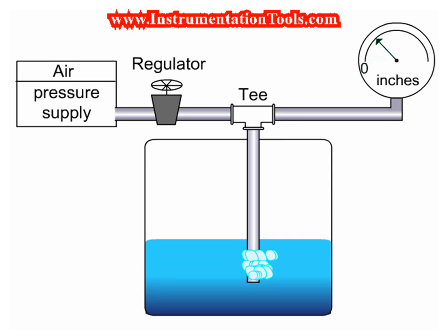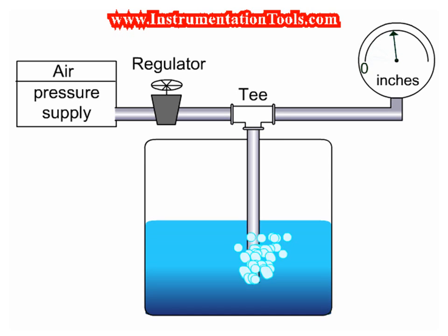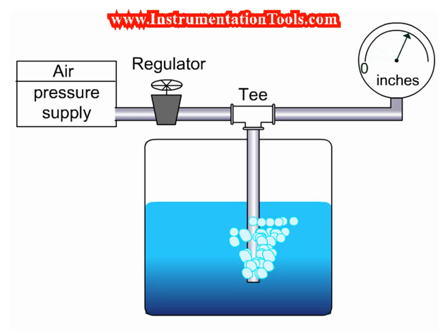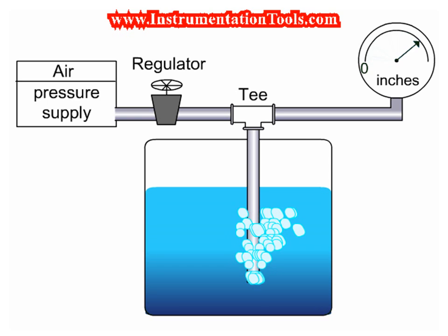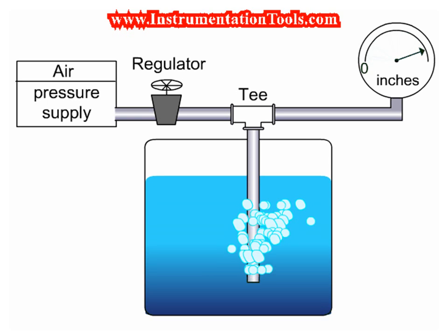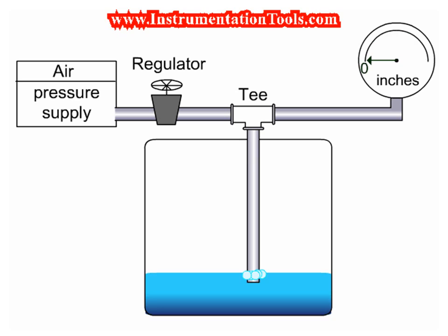When the tank level is higher, the back pressure increases. With the use of electronic transmitters, like pressure transmitters, we can convert the back pressure signal into a 4-20 mA level signal.